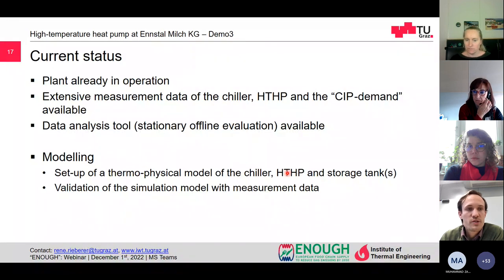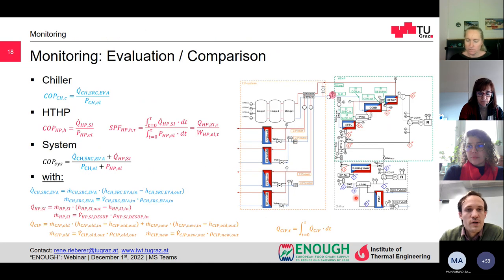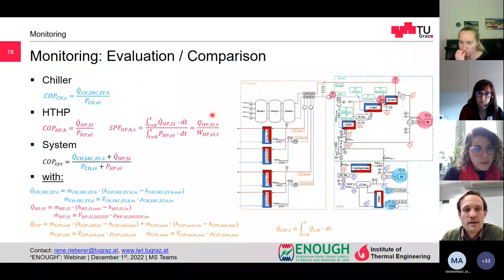There is a data analysis tool for the monitoring, and a simulation model has been set up of the chiller, the high temperature heat pump and the storage tank, which is already validated with measurement data. For the monitoring, a few key figures have been defined. So the efficiency of the chiller is the cooling capacity divided by the electrical power of the low pressure compressor. The same for the high temperature heat pump. There has also been a seasonal performance factor defined, which is the ratio of the amount of heat supplied divided by the electrical energy needed. And for the system, an efficiency has also been defined, which combines the chiller and the high temperature heat pump.